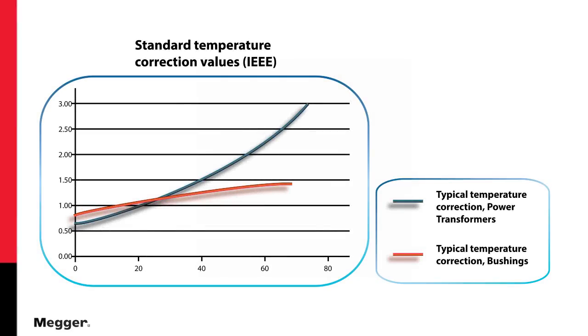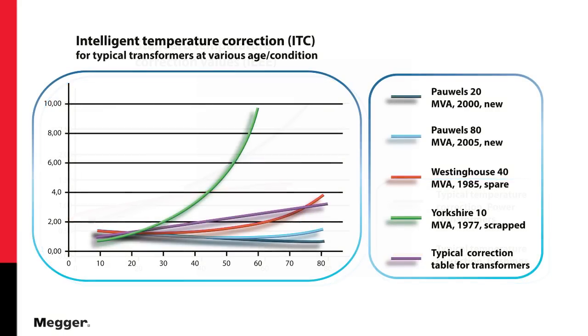Temperature correction graphs place all transformers and bushings into one or two categories, which is not accurate for many of our critical assets. As can be seen by this sample of actual temperature correction for various transformers, results can vary significantly.